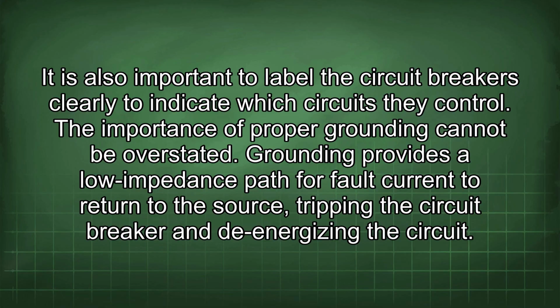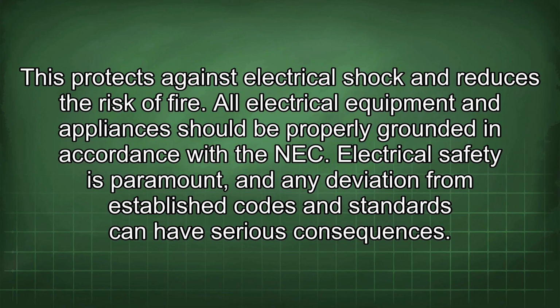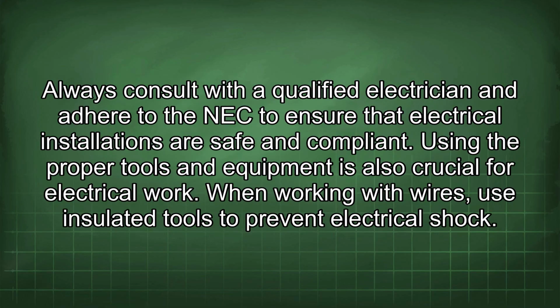The importance of proper grounding cannot be overstated. Grounding provides a low impedance path for fault current to return to the source, tripping the circuit breaker and de-energizing the circuit. This protects against electrical shock and reduces the risk of fire. All electrical equipment and appliances should be properly grounded in accordance with the NEC. Electrical safety is paramount, and any deviation from established codes and standards can have serious consequences. Always consult with a qualified electrician and adhere to the NEC to ensure that electrical installations are safe and compliant.